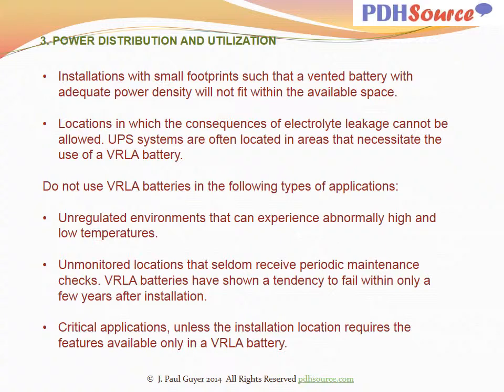Installations with small footprints such that a vented battery with adequate power density will not fit within the available space. Locations in which the consequences of electrolyte leakage cannot be allowed. UPS systems are often located in areas that necessitate the use of a VRLA battery.